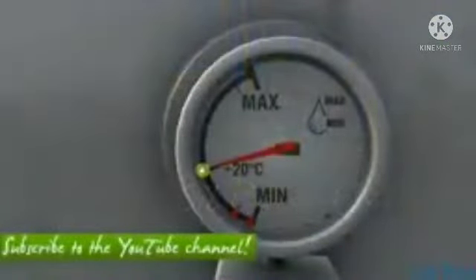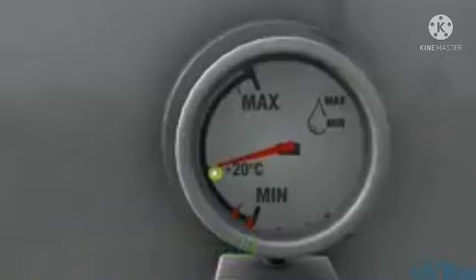We can see here the temperature. At 20 degrees we should have this level. So if we have 20 degrees now, the level will be here. As the temperature increases, the level will increase. This is not a temperature gauge, this is a level gauge. The 20 degrees Celsius is just for reference what the level should be at that temperature.